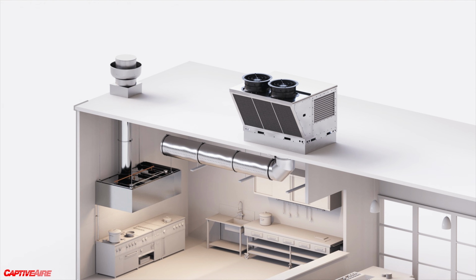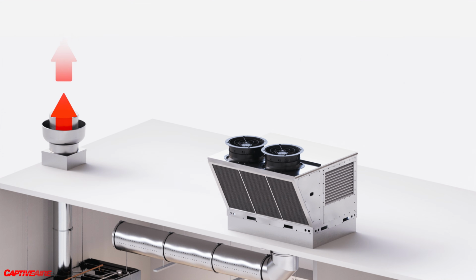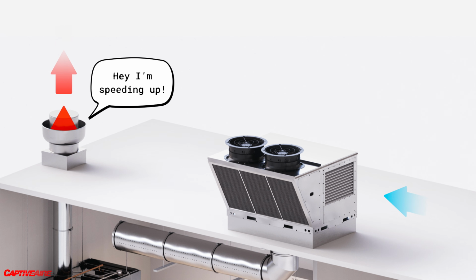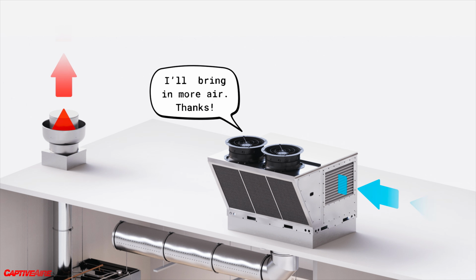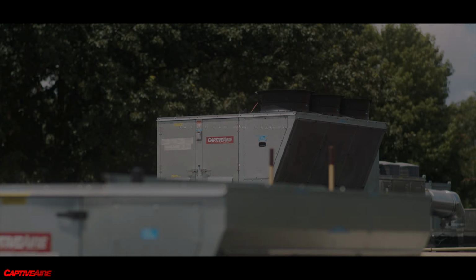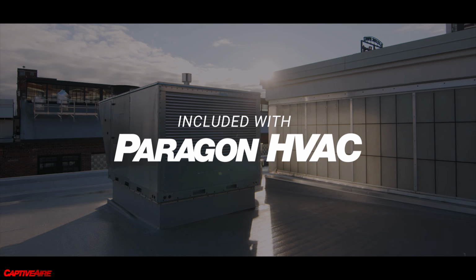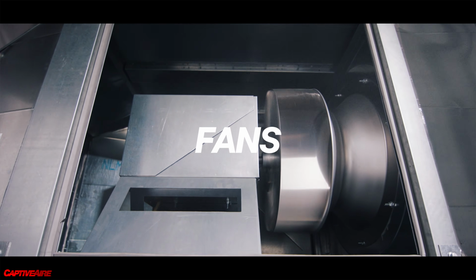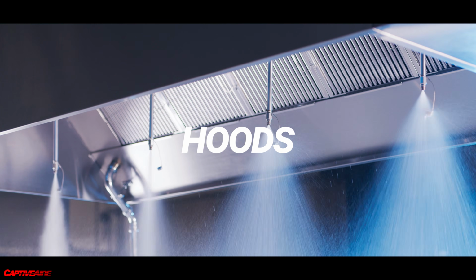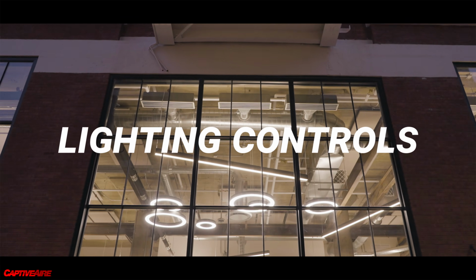Like in this restaurant, the operation of Paragon will be tied to what this hood and exhaust fan are doing. If the exhaust fan speeds up, then Paragon would have to bring in more outdoor air to make up for the additional exhausting air. Now, the hardware required to run CASLink is included in the cost of Paragon HVAC, but you can also add this option to our other products for a low price. And we don't charge you any fees to access the software.